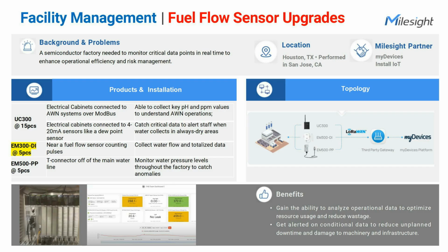A semiconductor factory in Houston was stuck with old-school sensors that couldn't wirelessly report data, like the ones monitoring humidity in their electrical cabinets. To fix this, they rolled out a smart upgrade. Firstly, for the real-time monitoring of critical systems, some UC300 controllers were installed to hook up to their existing equipment, such as connected to acid waste neutralization systems via Modbus for tracking the potential of hydrogen and parts per million values. And some UC controllers are connected to dew-point sensors that use 4 to 20 milliampere analog signals, sending alerts if water pools in areas that should stay bone dry.